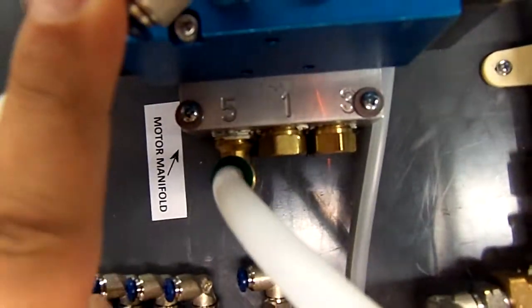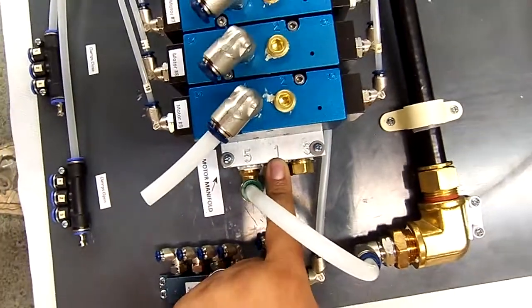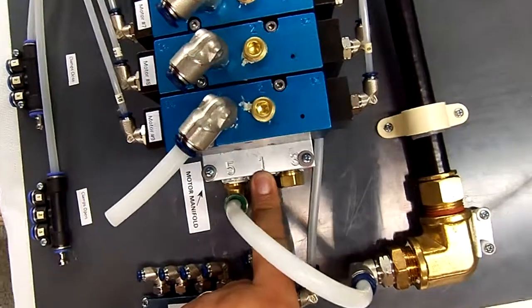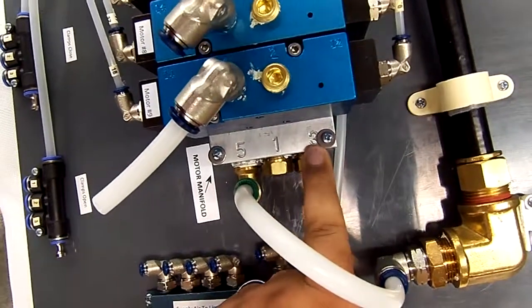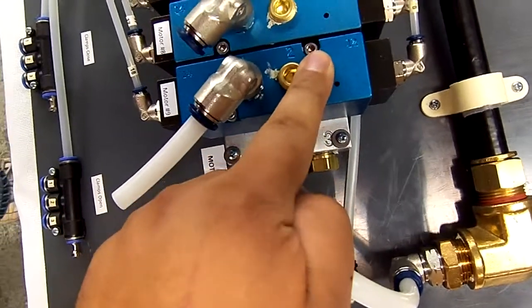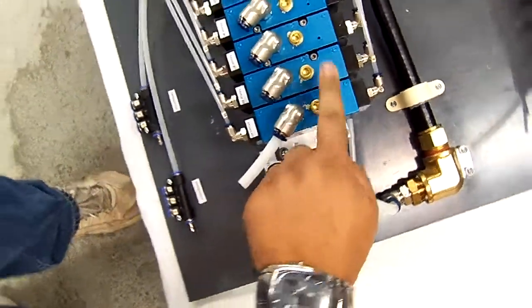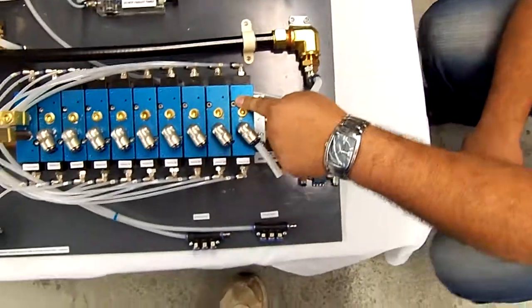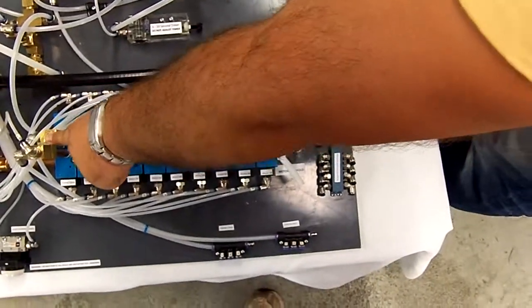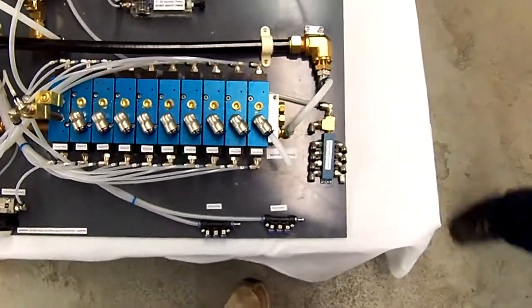Port 5 is reflecting the air supply for turning on the air motor. Port 1 is an exhaust. And number 3, if this were a drill valve it would control the retract, but in this particular case the only thing getting air on this port is the clamps to open.